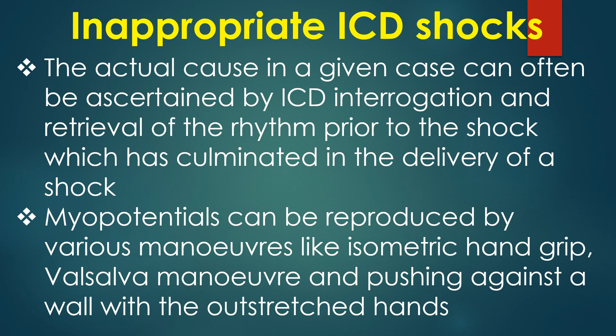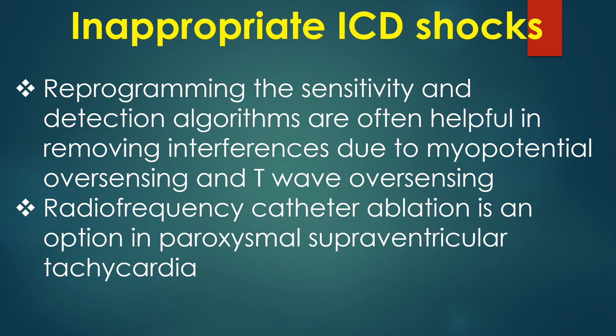Myopotentials can be reproduced by various maneuvers like isometric hand grip, Valsalva maneuver and pushing against a wall with outstretched hands. Reprogramming the sensitivity and detection algorithms are often helpful in removing interferences due to myopotential oversensing and T-wave oversensing. Radiofrequency catheter ablation is an option in paroxysmal supraventricular tachycardia. Lead fracture can be detected by image intensifier fluoroscopy and also indicated by an increase in lead impedance on interrogation.